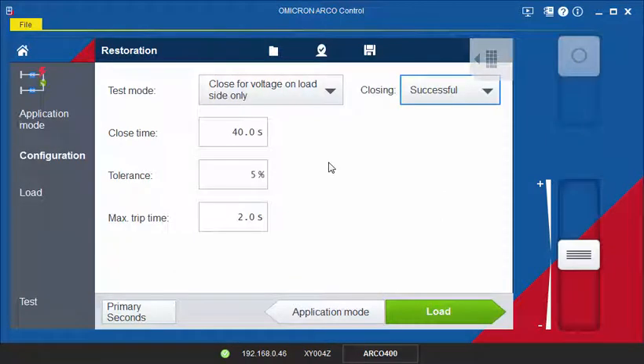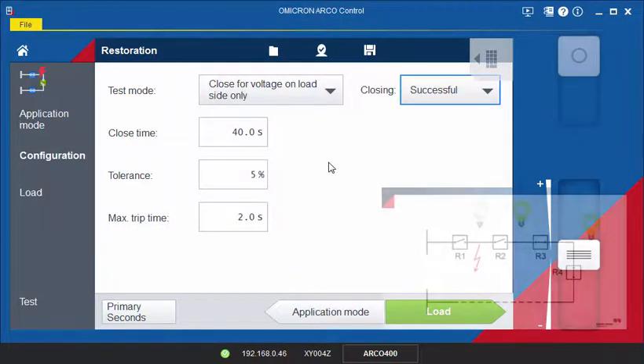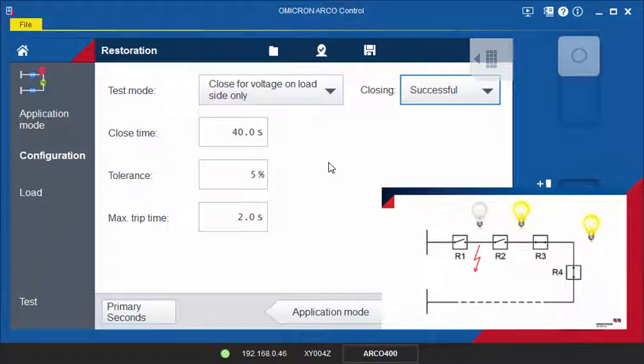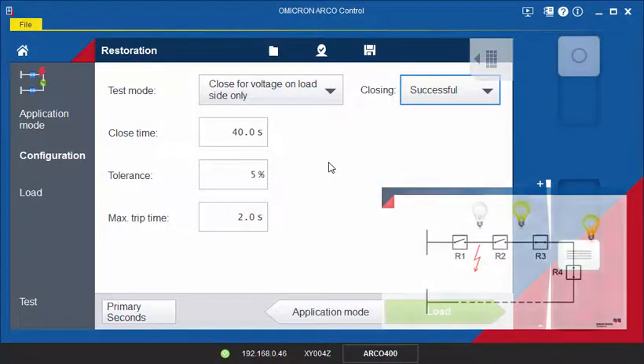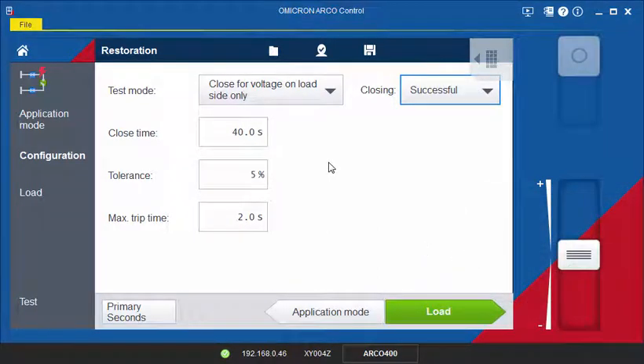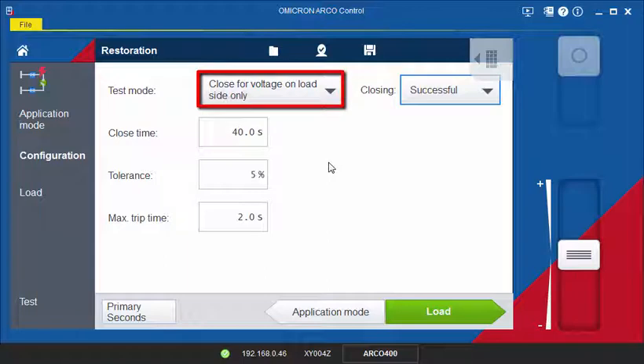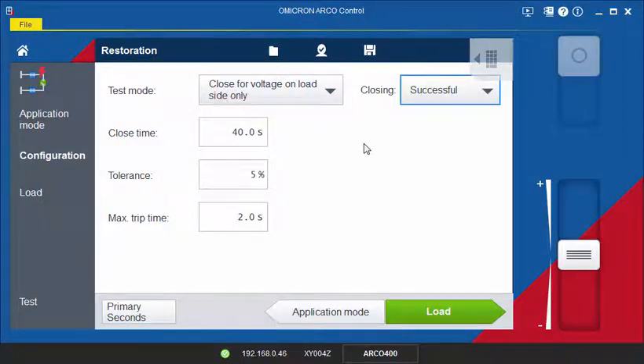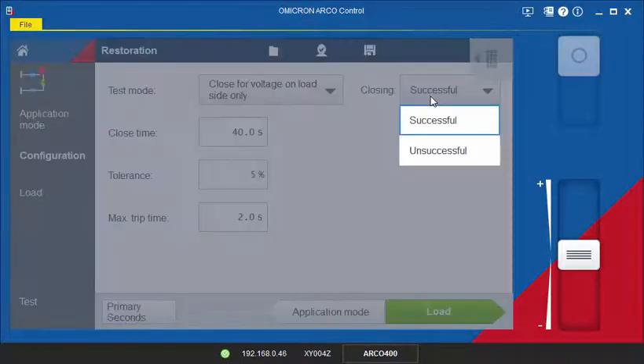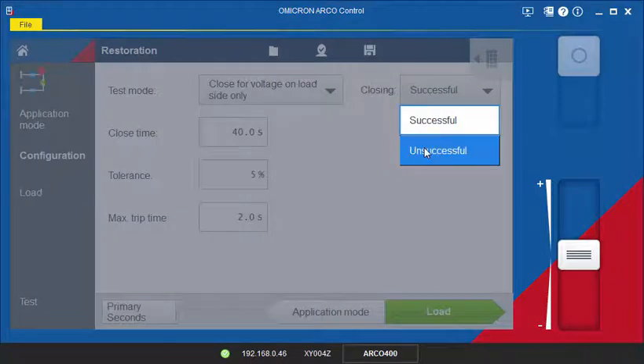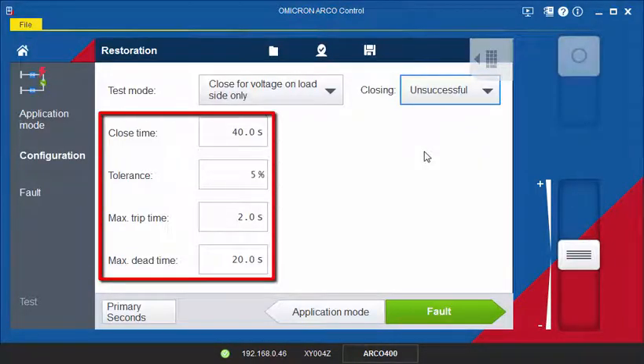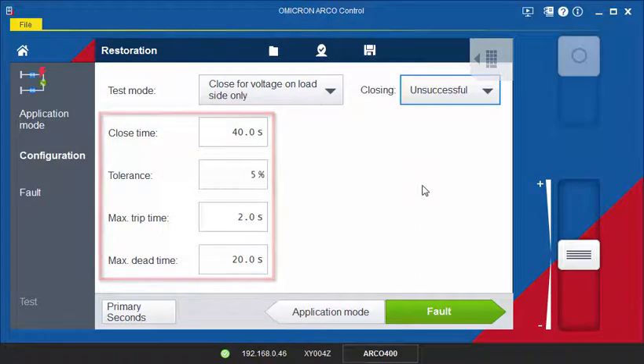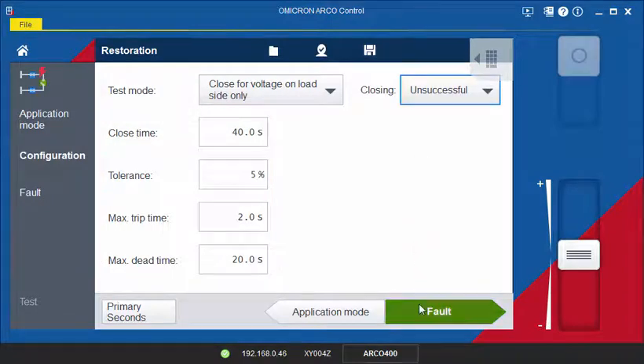The last step of the sequence in our example is the closing attempt of R2. R2 detects a voltage on the load side and attempts to close. R2 will not be able to close because the fault between R2 and R1 is still present. To test this behavior of R2, select Close for Voltage on Load Side Only as we did in the previous example, but this time select Unsuccessful Closing. Then, enter the Timing and Tolerance information.